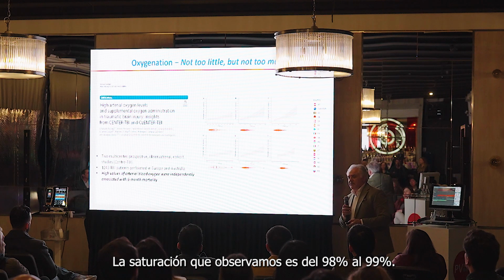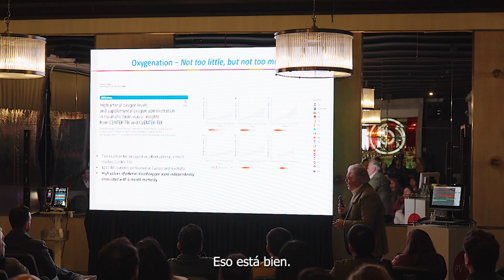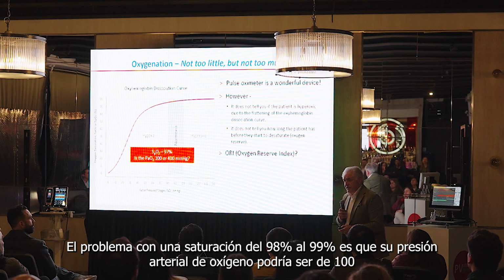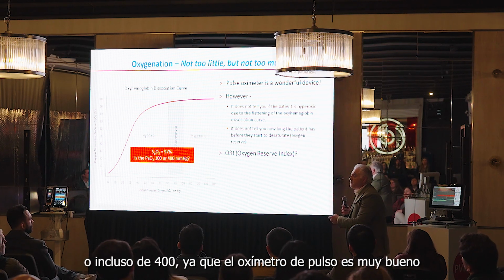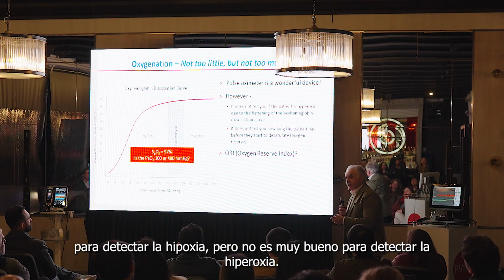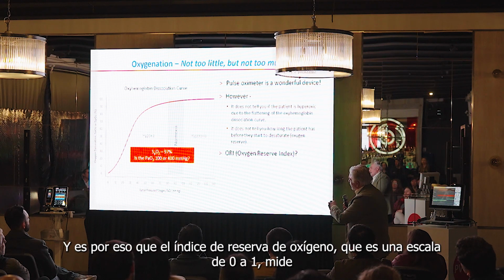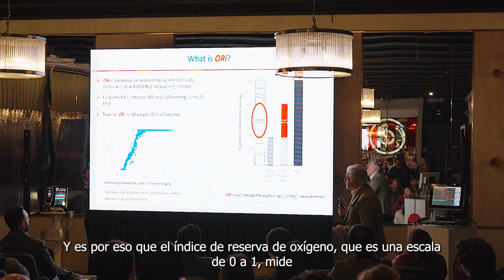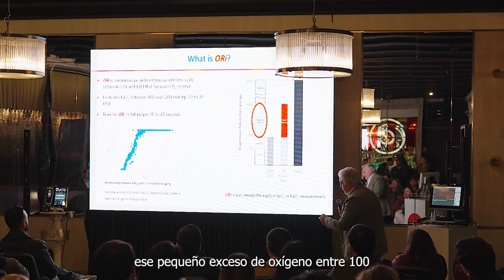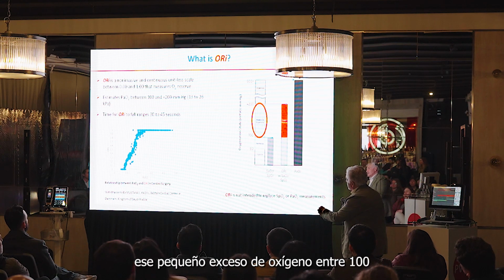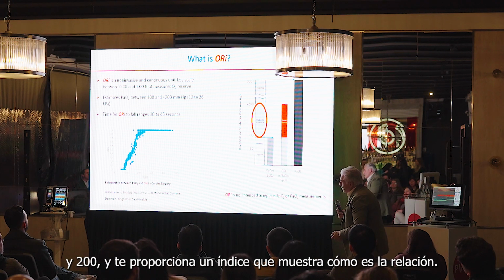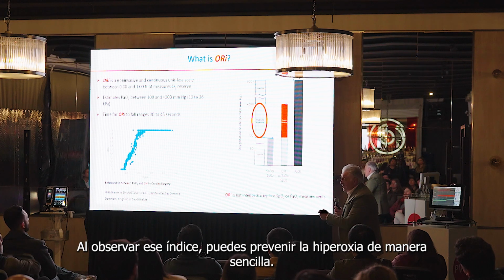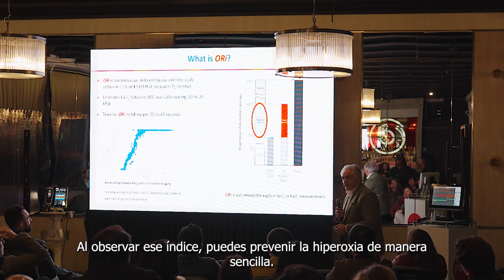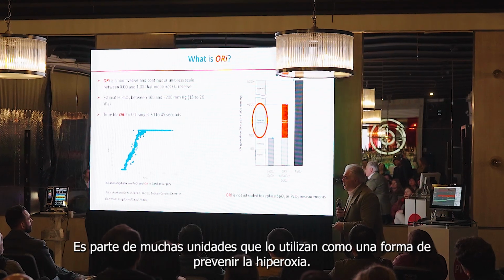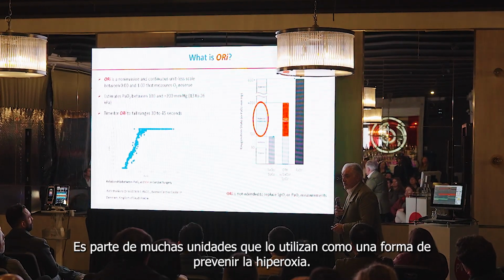The saturation we look at, 98, 99%, that's fine. The problem with a 98, 99 saturation is your PO2 could be 100 and it could be 400. Because the pulse oximeter is very good at detecting hypoxia, but it's not very good at detecting hyperoxia. And that's why the oxygen reserve index, which is a unitless index from 0 to 1, measures that little bit of oxygen between 100 and 200 and gives you an index to show how the relationship is. So by looking at that index, you can tell and prevent hyperoxia. And it's very easy. Many units are now using it as a way of preventing hyperoxia.